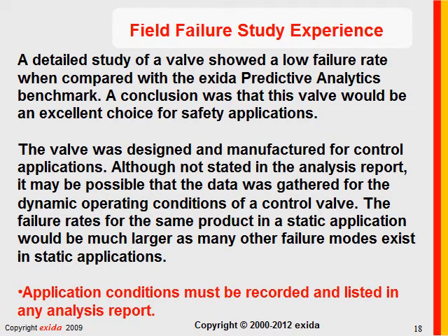There's more. I have dozens and dozens of stories, but you don't have time for all of them today. A detailed study of a valve showed a low failure rate when compared with the exida Predictive Analytics benchmark. Our conclusion was this particular valve would be an excellent choice for safety applications, and the sales department of the valve manufacturer got very excited. The valve was designed and manufactured for control applications. Okay, fine.